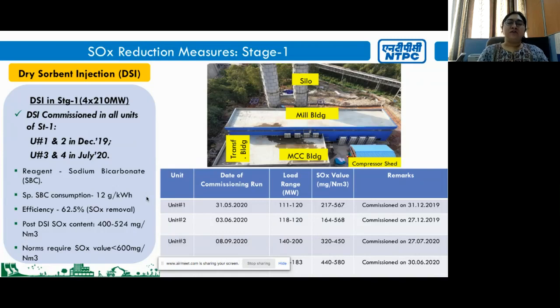Coming to SOx reduction technologies, in stage 1, we have installed dry sorbent injection system, and it has been commissioned in all the 4 units. In dry sorbent injection, we use sodium bicarbonate as a reagent. It reacts with acid gases in flue stream and forms unharmful sulfate products which can be removed in fly ash. The specific consumption of sodium bicarbonate is 12 grams per kilowatt hour, and the efficiency of this SOx removal system is around 62%. And these are the values in the table. We have shown the values of the test run for all the units, and we have been able to achieve SOx values less than 600 milligram per normal meter cube.